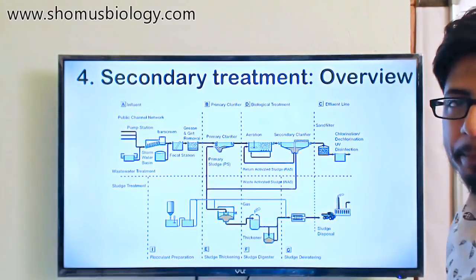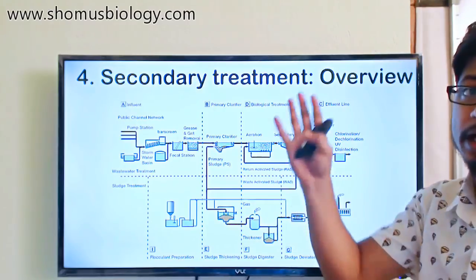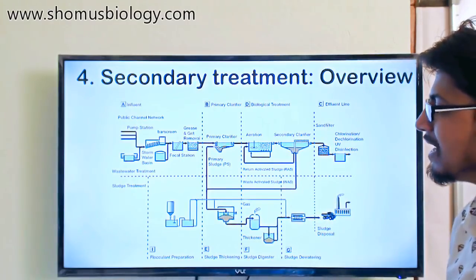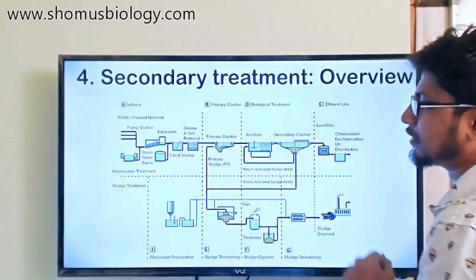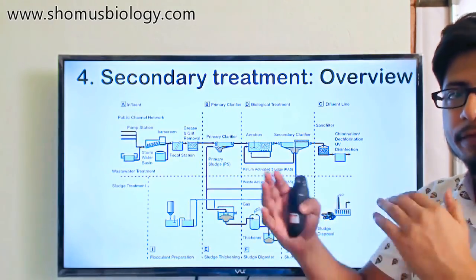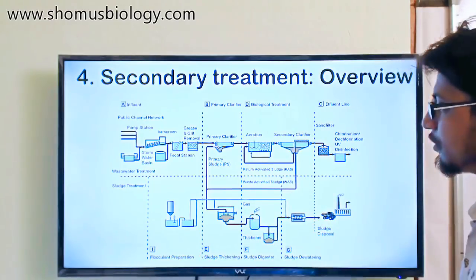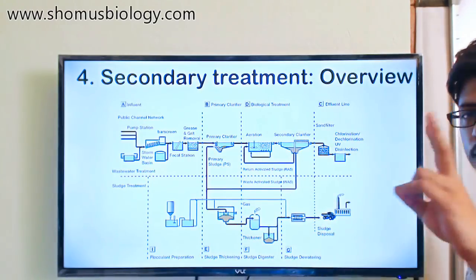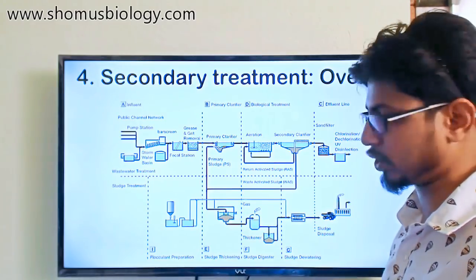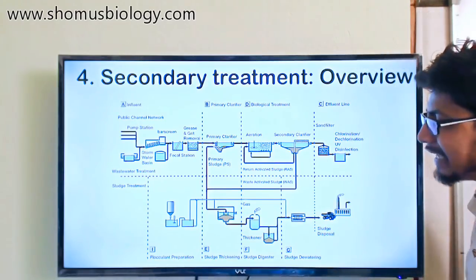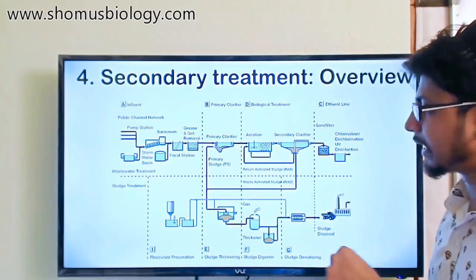In the big picture overview of a wastewater system, after the preliminary and primary treatment, the effluent comes into the secondary treatment. In the secondary treatment there are two different components: one is the aeration chamber, and after the effluent is aerated it is transported to the secondary clarifier, which is a large tank like the primary clarifier.